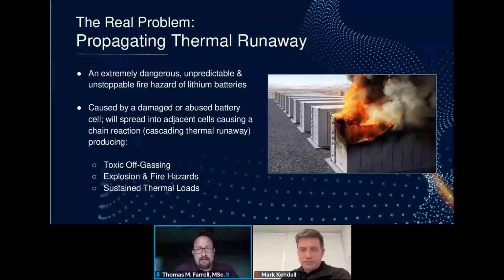And all of this results in severe levels of toxic off-gassing. It causes explosion and fire hazards. What's also concerning is sustained thermal load. So if this is near another structure or inside of one, it can cause the fire to propagate outside of the ESS or battery backup if it's a smaller scale system.